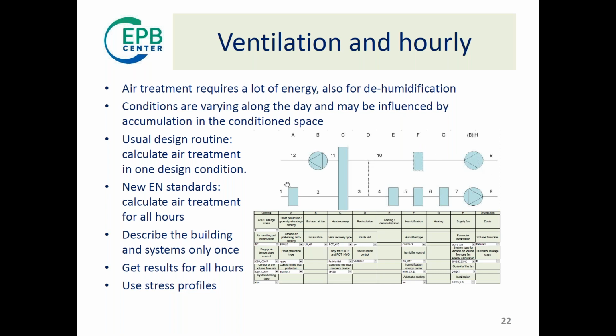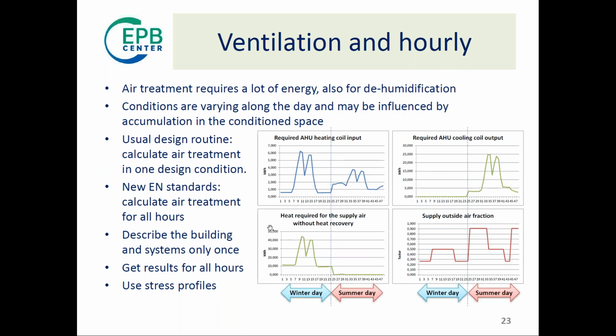So you have these schematics, and you have the options to describe your technical system. And that's not peanuts, because you can see here these resulting graphs, and the graph is constructed so that the first 24 hours are a winter day and the second half is a typical summer day. Just have a look at the scale. Here is your heating coil input: you see 6,000 kilowatt hours, and here for cooling 25,000 kilowatt hours. So four times more for cooling and dehumidification. And without the heat recovery, you would have a very high energy use. All this calculation is done hour by hour.